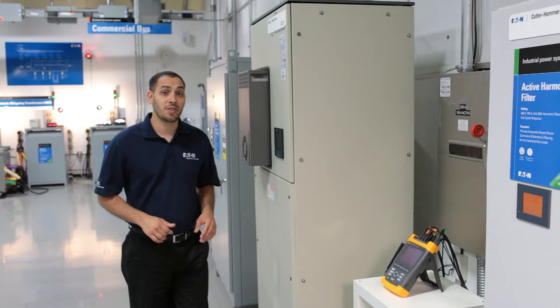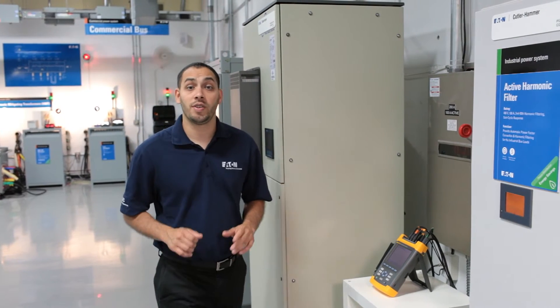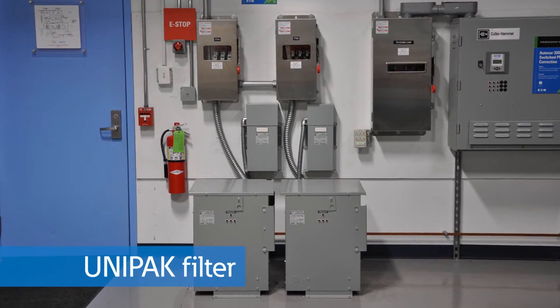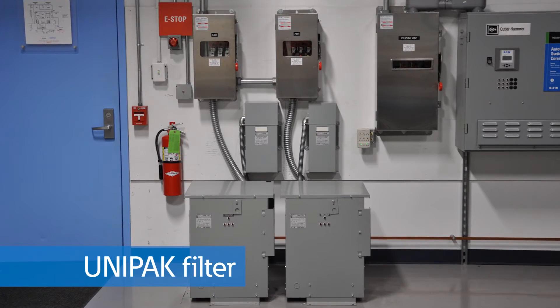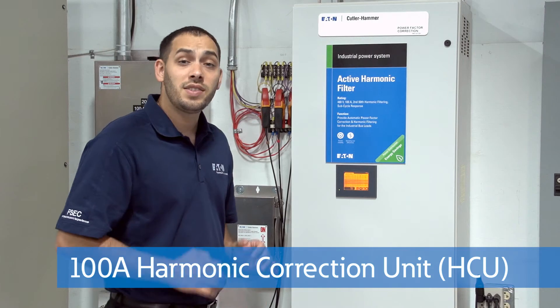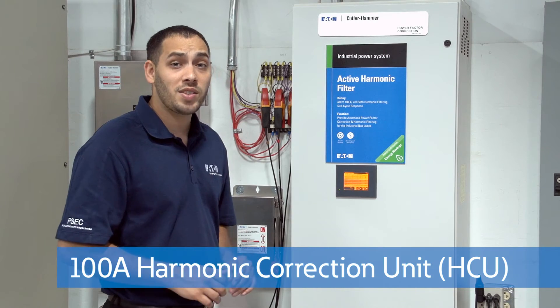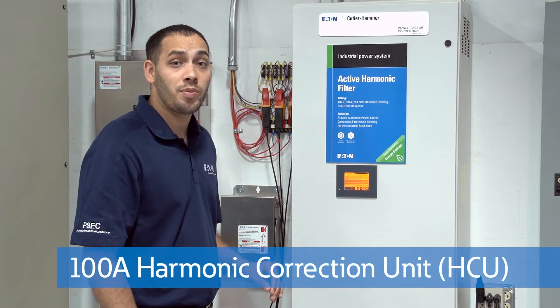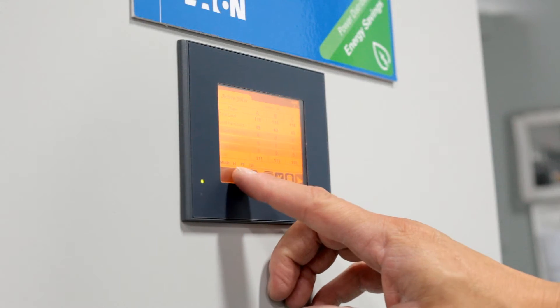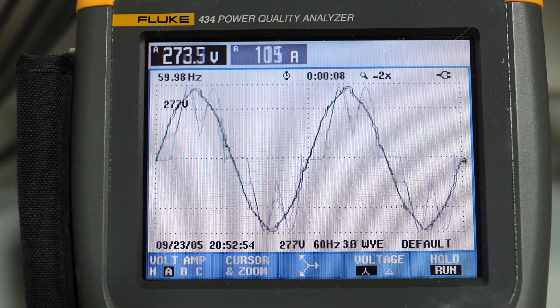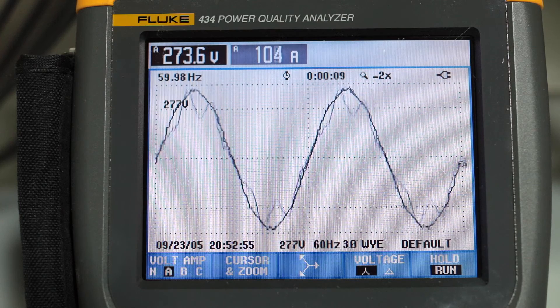There are several options available to reduce the harmonics in your system. A passive filter, such as this one, can be used to reduce the current of one or two harmonics. In systems with complex harmonic signatures or varying processes, active harmonic filters are a very effective solution. However, they are one of the most costly solutions.